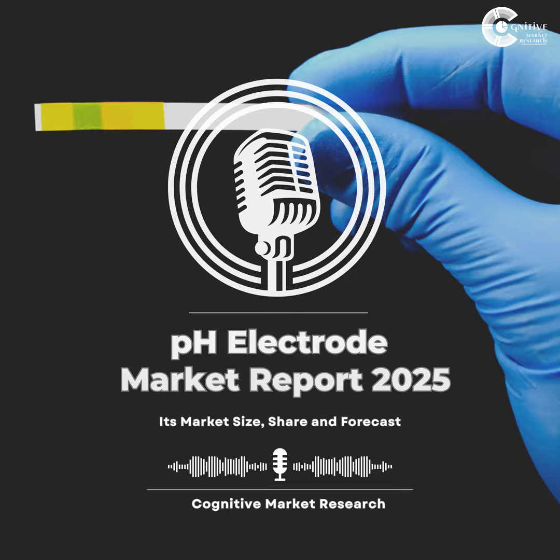What's the magic? Yeah, it's quite ingenious, actually. At its core, a pH electrode is measuring electrical potential difference. It's basically created by the concentration of hydrogen ions in whatever solution it's in. You can sort of think of it like a tiny specialized battery. It generates a voltage, and that voltage is directly proportional to the pH level. So it's a really clever way to translate chemistry, essentially, into an electrical signal. And that gives us that precise pH reading that, well, so many industries rely on. That makes perfect sense, like a little chemical translator.